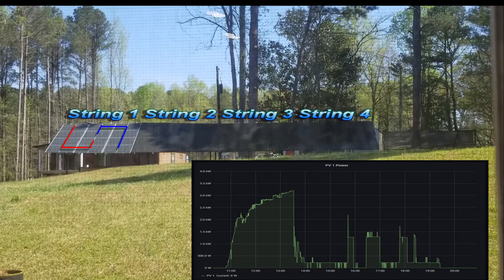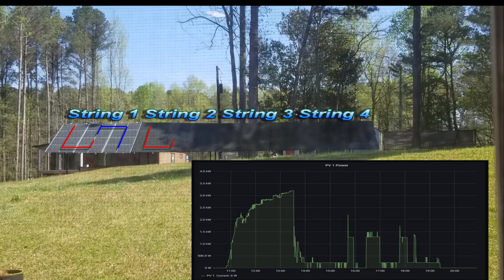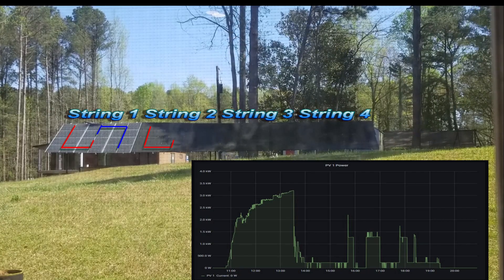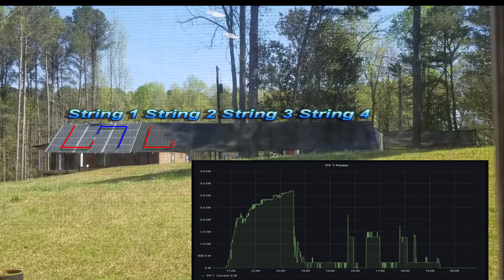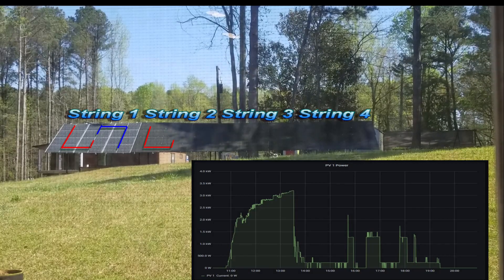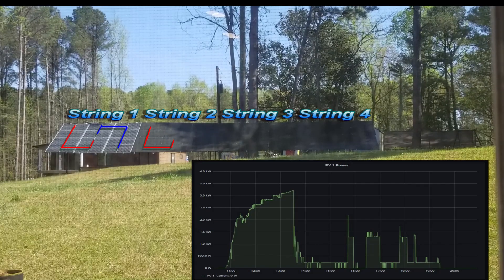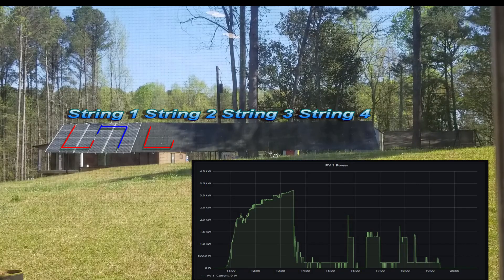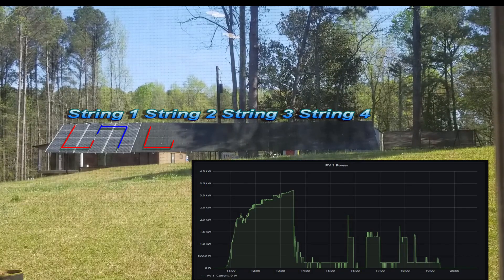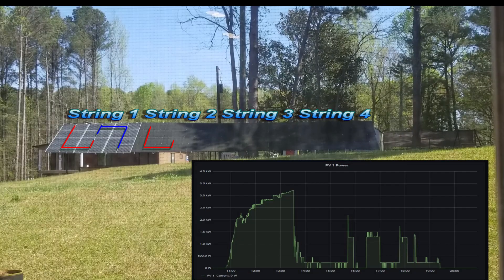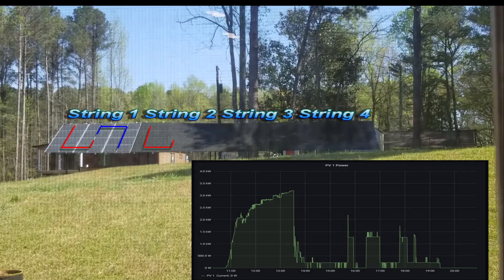I had all winter to ponder on this and see how I was going to set them up. I decided to do it this way so I could avoid buying DC optimizers for the panels. I think this is the best solution without spending extra money on additional equipment and introducing another failure point somewhere in the system.